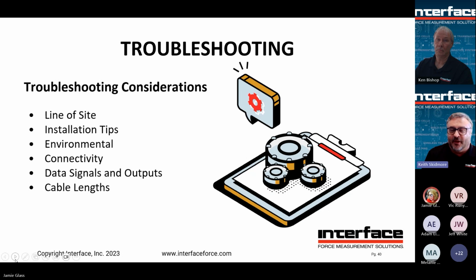You look at all of the items in the load string. Environmental: certain load cells are more suited for cold or wet environments. So if you have, say, premature failure, it could be that the load cell or the lifting device measurement system wasn't rated for the environment. Connectivity: load cells output signals. Those signals have to be converted or read by something else. And so if something's not working, it may or may not be the load cell or the lifting device. It could be the cabling or the wiring, that the cable may not be wired to the reading device correctly. It could be that the actual reading device isn't calibrated or scaled, or could be damaged. So it's important to consider the entirety of the system and then try to isolate which device may or may not be the issue.